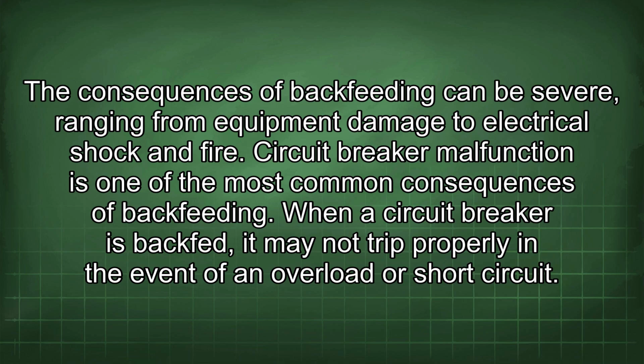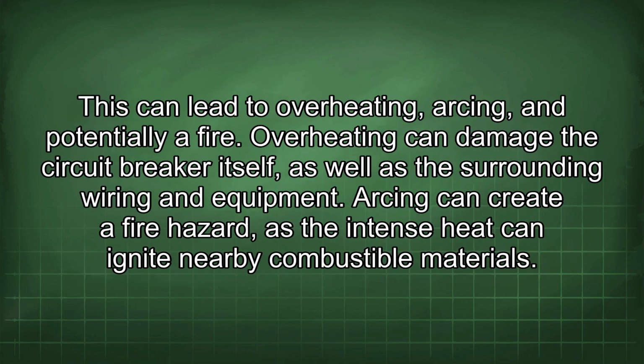Circuit breaker malfunction is one of the most common consequences of backfeeding. When a circuit breaker is backfed, it may not trip properly in the event of an overload or short circuit. This can lead to overheating, arcing, and potentially a fire. Overheating can damage the circuit breaker itself, as well as the surrounding wiring and equipment. Arcing can create a fire hazard, as the intense heat can ignite nearby combustible materials.